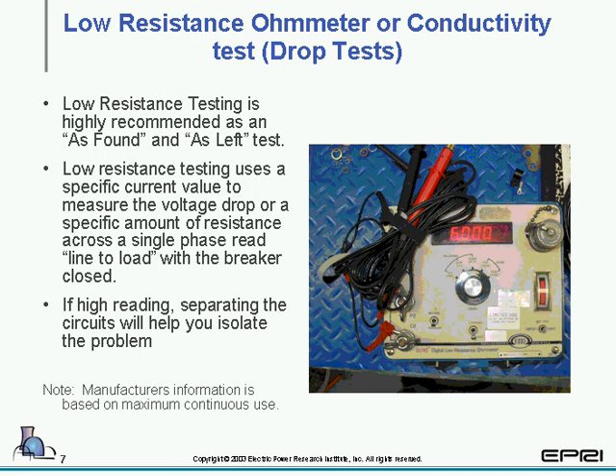And we've also had challenges with this particular test not meeting the minimum manufacturer's recommendation, contacting the manufacturer and them saying, that's okay. When you're running your equipment, the instruction manuals are written with a cushion. So they're more concerned that you're running the piece of equipment at its peak operating load. So, for example, if it's a 600 amp breaker, that particular ohmic value or low resistance value is if you're running that circuit breaker at 600 amps. If you're running it less than that, you need to be less concerned. But again, you must use common sense.